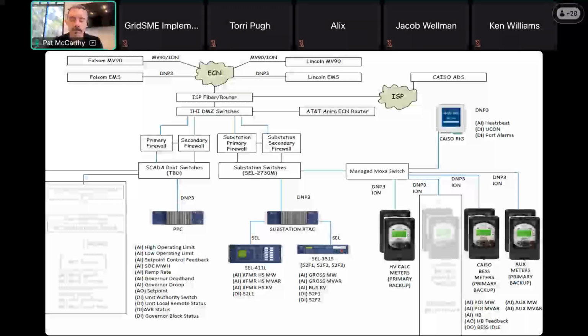Depending on the backfeed status of your site, whether or not you're actually connected to the grid by the time you do the point-to-point from a utility perspective, you may or may not operate the breaker points from the relay. CAISO doesn't want you to actually open and close breakers, but they want the device that monitors those breakers to report the data all the way through the system.